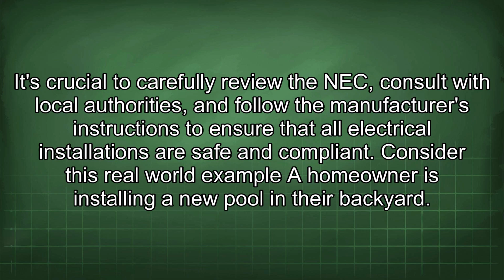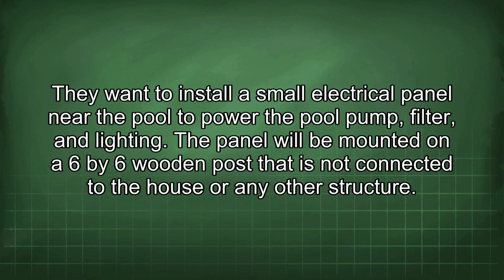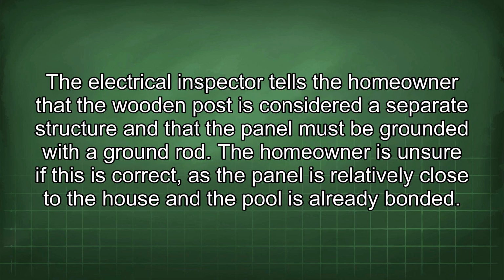Consider this real-world example: a homeowner is installing a new pool in their backyard. They want to install a small electrical panel near the pool to power the pool pump, filter, and lighting. The panel will be mounted on a 6x6 wooden post that is not connected to the house or any other structure. The electrical inspector tells the homeowner that the wooden post is considered a separate structure and that the panel must be grounded with a ground rod.